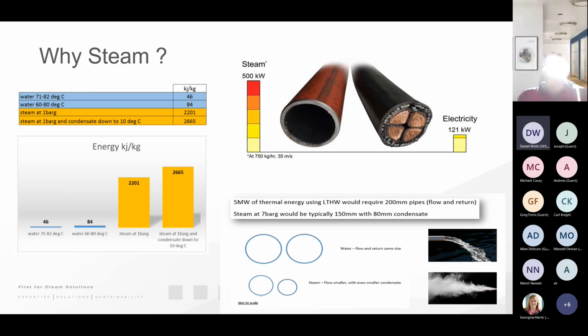If we compare that to low temperature hot water as an alternative, yes, we've got less energy in the water. Yes, we need a bigger infrastructure. We're also going to need to provide a circulating pump in order to move the energy from the point of generation to the point of use. So we're going to be drawing more energy, more electricity, in order to move that heat.